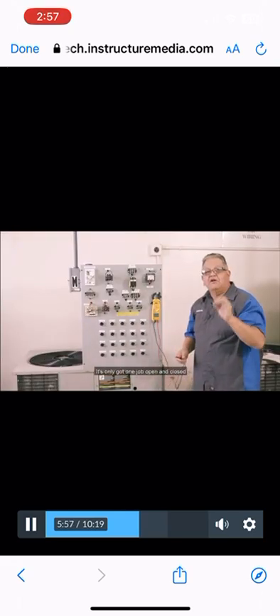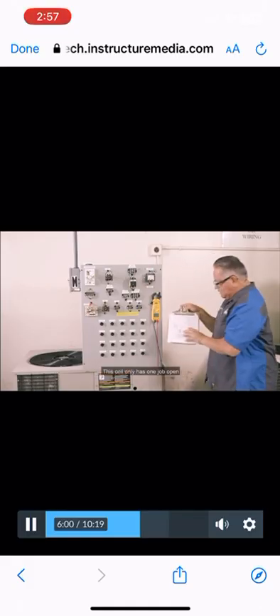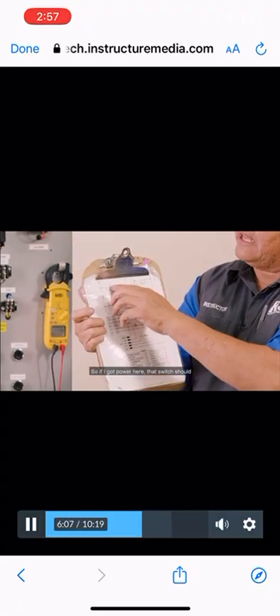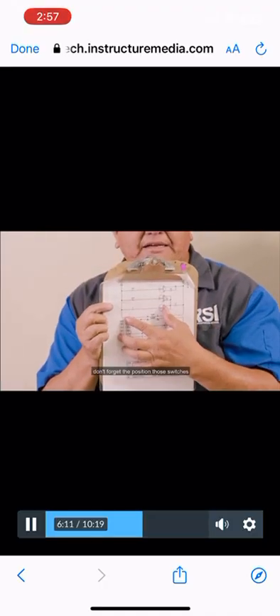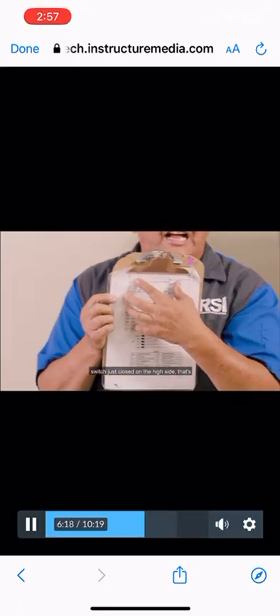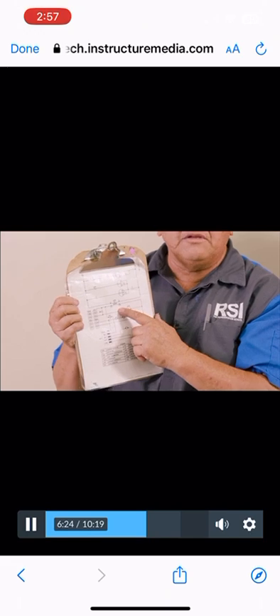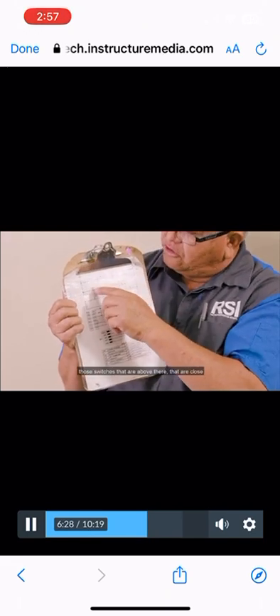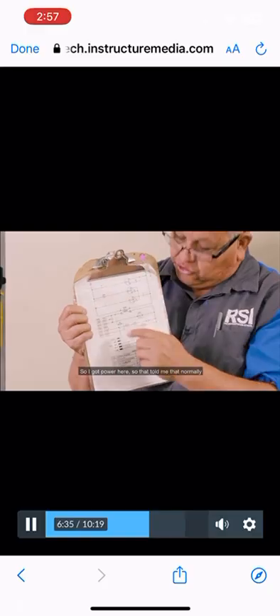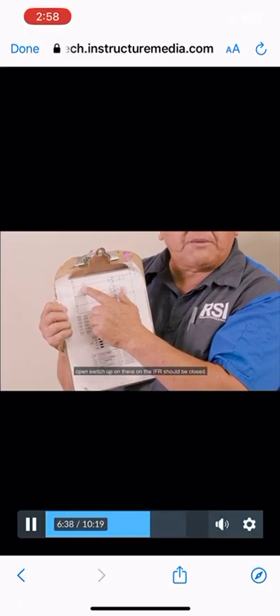I got 24 volts. What's that coil's job? It's only got one job: open and close switches. This coil only has one job: open and close that switch. So if I got power here, that switch should be closed. Remember, when you look at a schematic, don't forget the position those switches are in. When you see a switch that's open or you see a switch that's closed on the high side, that's the position that switch should be when there is no power applied to these coils. So when I don't have power applied to these coils, those switches that are above there that are closed should be closed. The switches that are open should be open. So I got power here, so that tells me that normally open switch up on there on the IFR should be closed. Let's find out if it's closed.